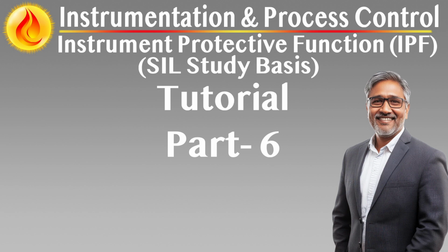Fire and gas system (FGS) coordination. In some cases, FGS signals may trigger IPFs or be triggered by IPF activation, e.g., coordinated blowdown or shutdown. These integrations must be designed using hardwired or safety-rated communication protocols and tested for deterministic behavior.